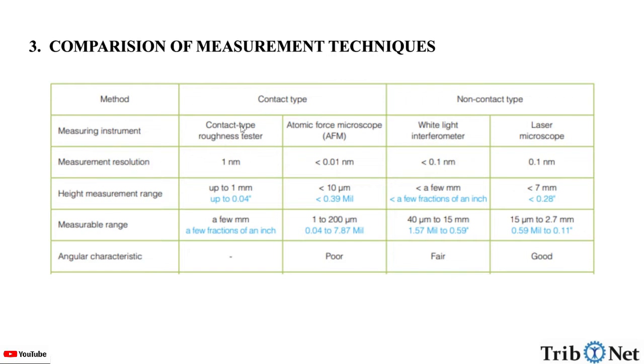Measurement resolution for contact type is 1 nm for stylus and less than 0.01 nm for atomic force microscopy. For non-contact type, optical interferometer is less than 0.1 nm and laser microscope is 0.1 nm.